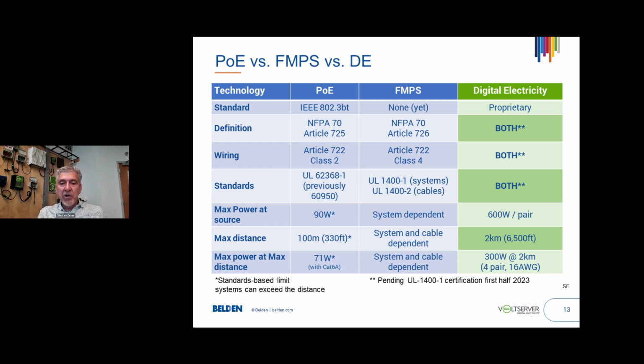So in terms of Article 726 qualification, as many of you know, something has to be listed to be installed in buildings in the United States and in Canada. And so that listing standard is currently being evolved. So the testing for these systems is going on now with more than one manufacturer. And we expect on the VoltServer side, somewhere around the first half of 2023, we'll obtain our certifications under the new standards, and then it can install under Article 726 in the municipalities that have adopted it.